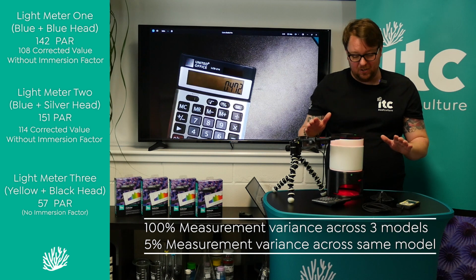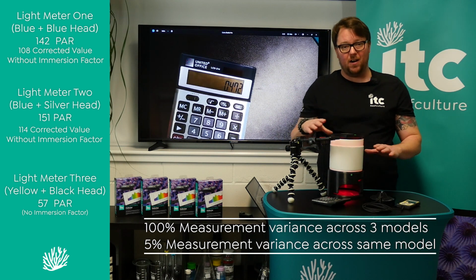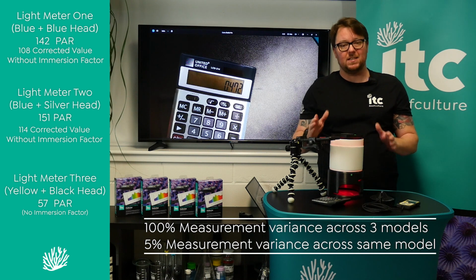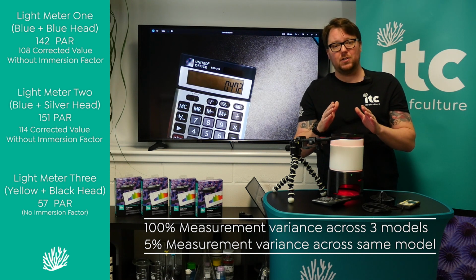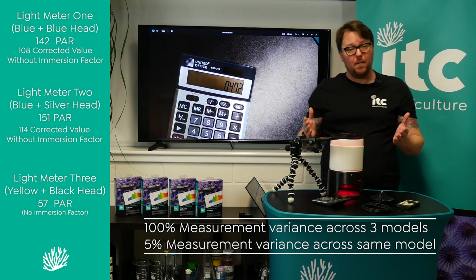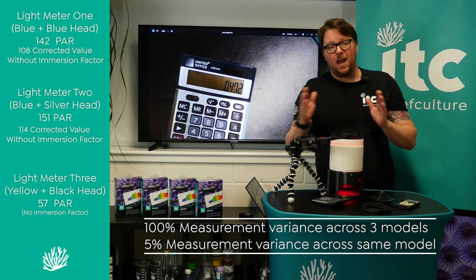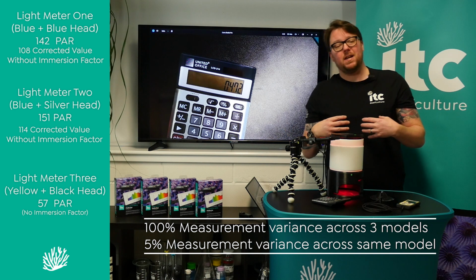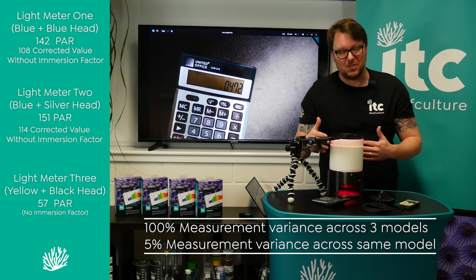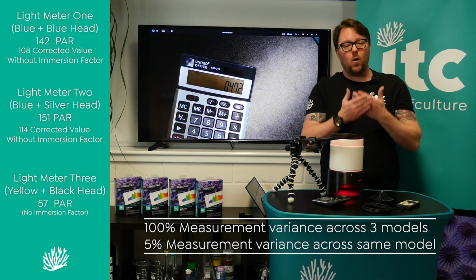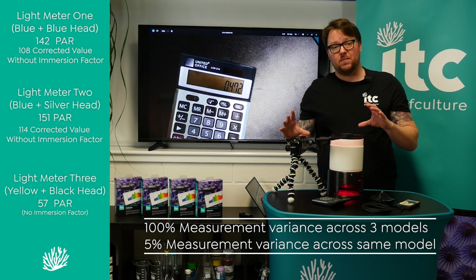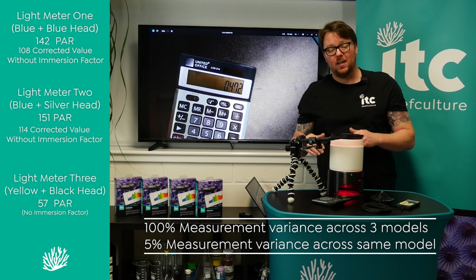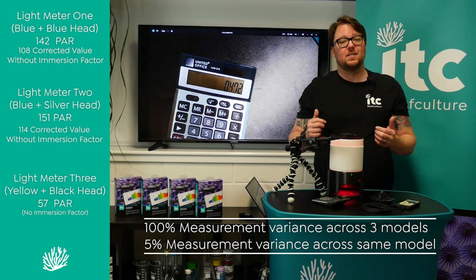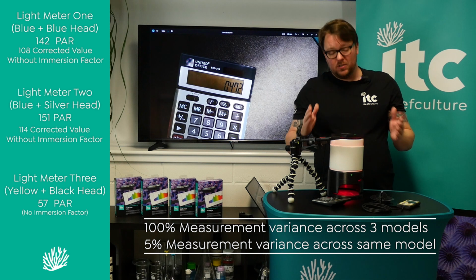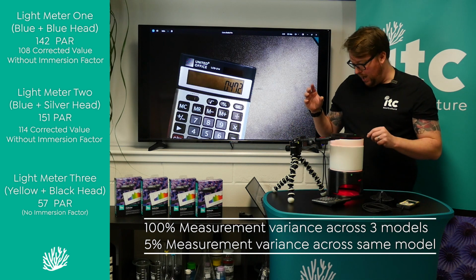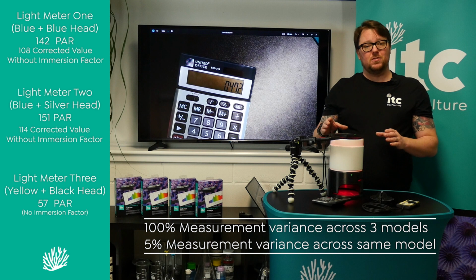We're not using this to say that these models of light meter are rubbish, but the main difference is if there is a single point of calibration, which these particular light meters are done with, their results can vary across the spectrum. And I know as a reef keeper myself that I'm not really using red light and I'm not using green, but if you have a white LED, those are all parts of the spectrum that are being put into the tank. So they are relevant, and then they can make the differences between your light measurements. So the point being, the model that you use makes a massive difference in those results.